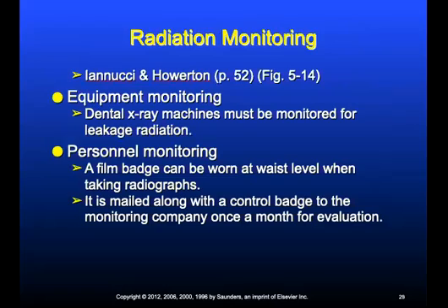Radiation monitoring devices should be worn by all dental radiographers. Dental X-ray machines should be monitored for leakage radiation as well. So that means that you are wearing a radiation monitoring device, but that doesn't mean that your equipment shouldn't also be monitored for radiation leakage, as this can sometimes leak through bad collimators and things like that.